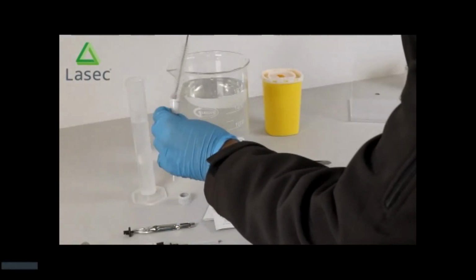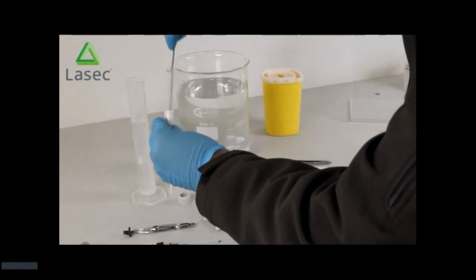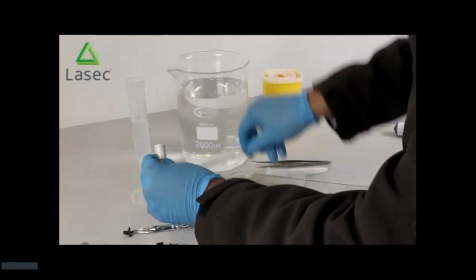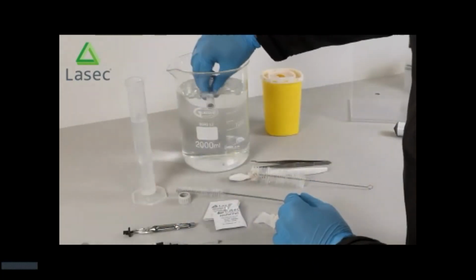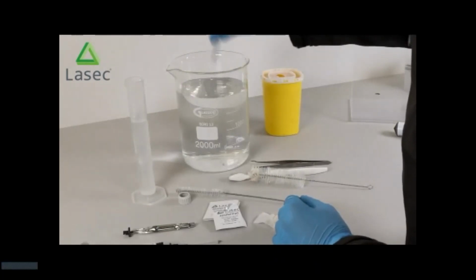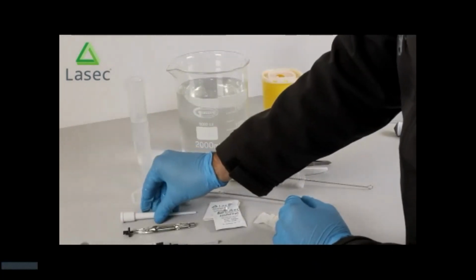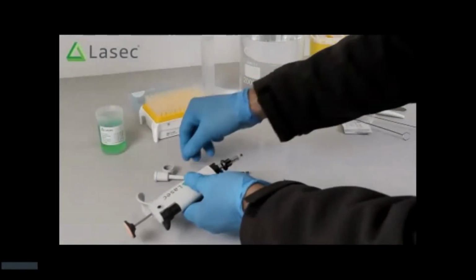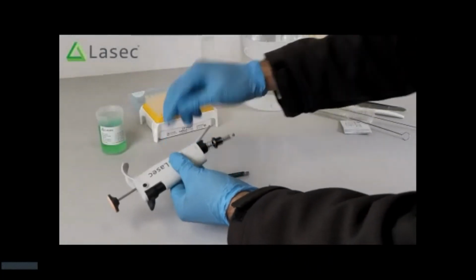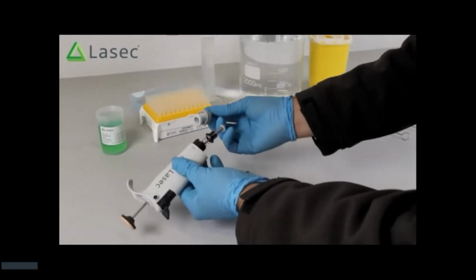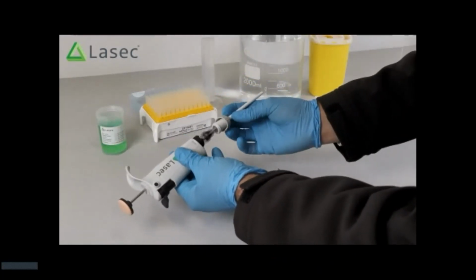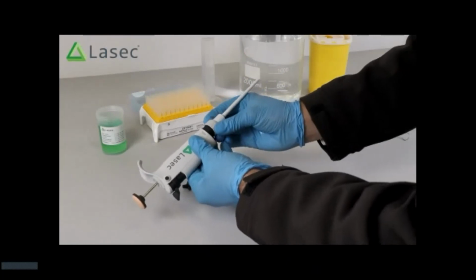So in some cases with tip holders, if they are wide enough, you can get these bottle or bristle brushes that you can use to physically and mechanically remove any contamination inside of those tip holders. Generally speaking, with the smaller volume pipettes, you have a very narrow tip holder. They are more difficult to clean than your larger volume pipettes.